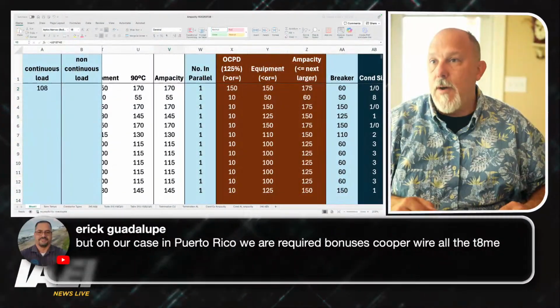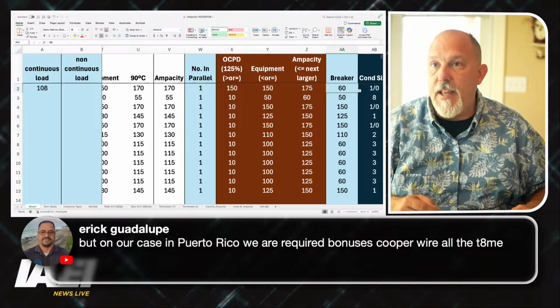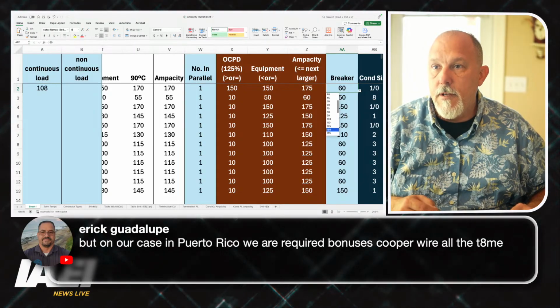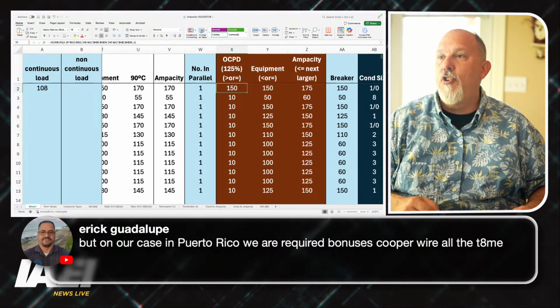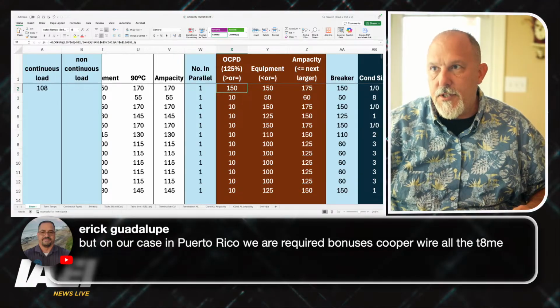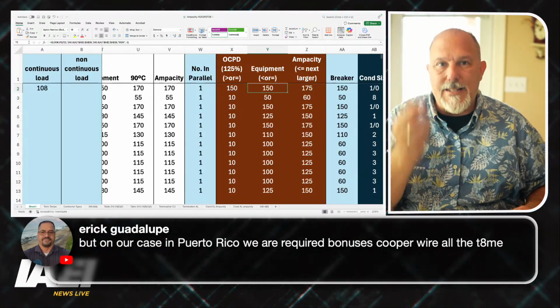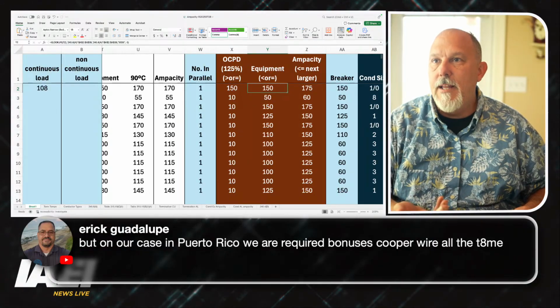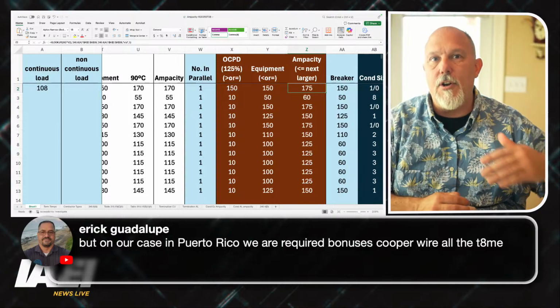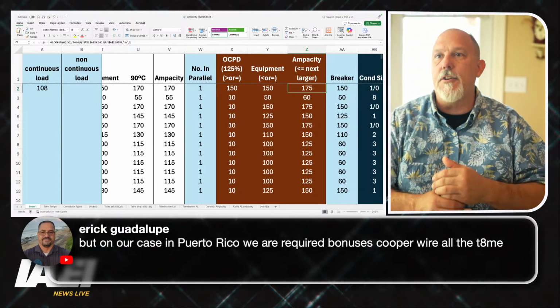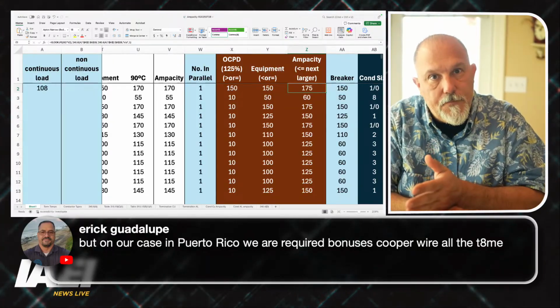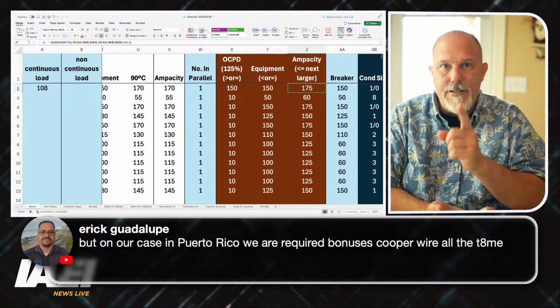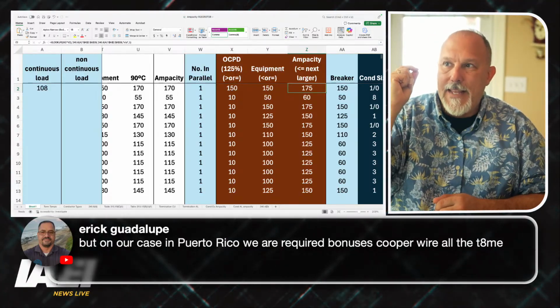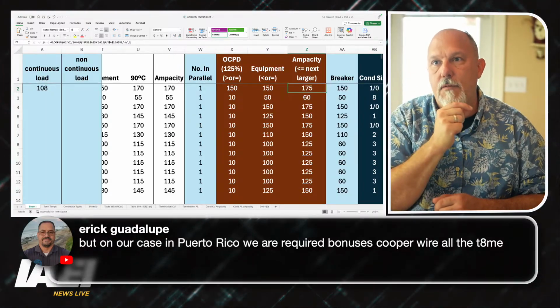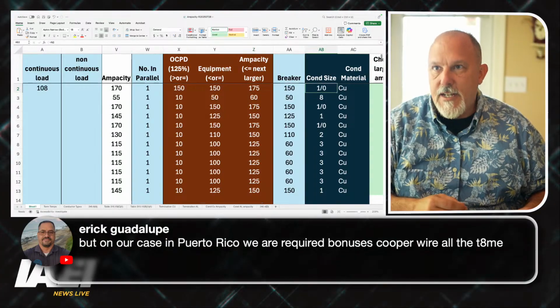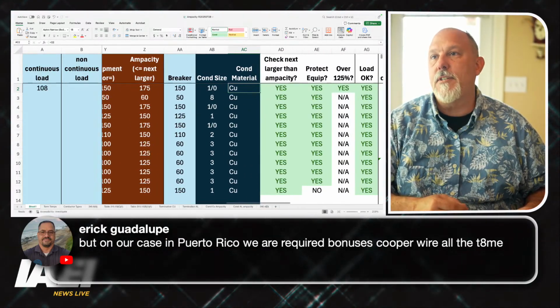All right? So I'm going to pick a 150 amp circuit breaker because it is greater than or equal to the 135 continuous. It is less than or equal to the equipment rating, that's the 75 degree C column, which is 150 amps. And it is less than or equal to the next larger overcurrent protective device from the ampacity of the conductor. So a 150 amp breaker is going to protect the conductor, it's going to protect the termination, and it's large enough so that the continuous current doesn't exceed the rating of the overcurrent protective device. My conductor size is a 1-aught, it is copper, and then I do my comparisons.